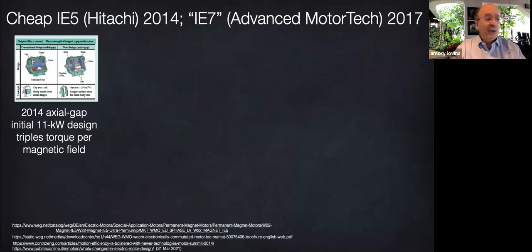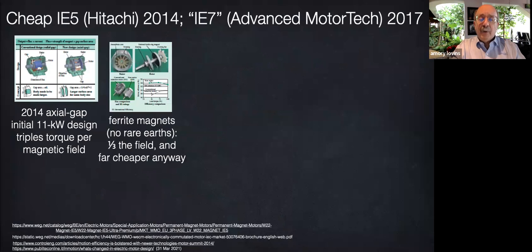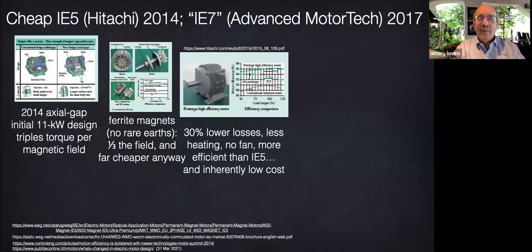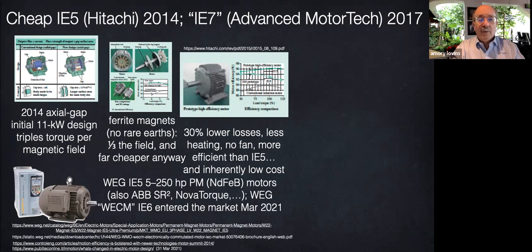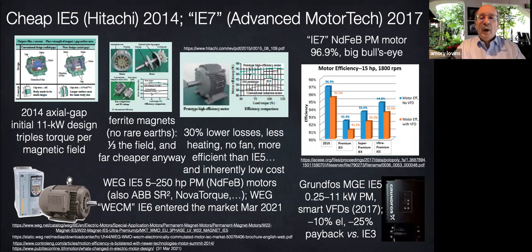In 2014, Hitachi developed a short axial flux 11 kilowatt motor whose amorphous iron core, kind of glassy iron, cut the iron losses by 90%. And then cheap ferrite magnets instead of rare earth magnets could get the same torque out of 1/3 the field strength. The 30% lower losses eliminated the cooling fan, saving more energy and downtime. And the ferrite magnets are very much cheaper than the rare earth magnets used in commercial ABB and Brazilian and Danish motors. And by 2017, a rare earth magnet motor equivalent to a conceptual IE7 standard, 2 notches above the top actual standard, had been demonstrated.